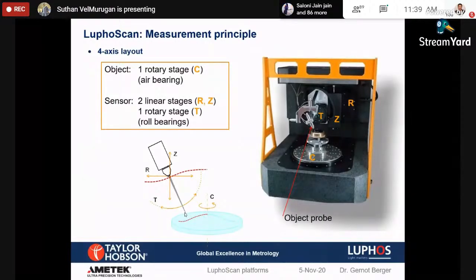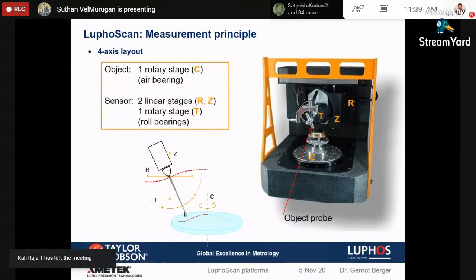So in this sense, we need to define what radius we are going to measure and what the form shape is. It is a concave aspheric. We need to define everything before starting the measurement. The optical probe will tilt each and every time the spindle rotates, and according to the part, normal to the surface, it keeps tilting. It can tilt up to 90 degrees, so that we are able to measure even steep slopes or hemispheres. We can measure from 0 degrees to 90 degrees horizontal, so that we can measure the entire hemisphere.